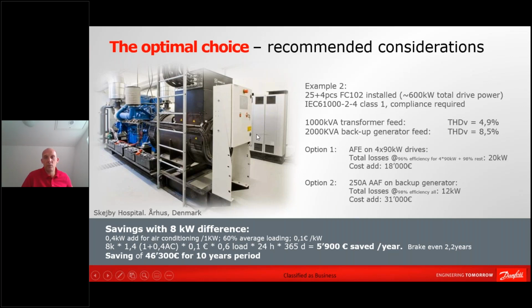And when we do the calculation, you can see that the mitigation again was only needed when you're running a backup generator, even though the generator was much bigger than the transformer, actually twice the size. You can see that the impedance of the generator simply makes the voltage distortion go up. And again here, instead of adding a lot of mitigation equipment, you could add one single filter that only runs in emergency mode.